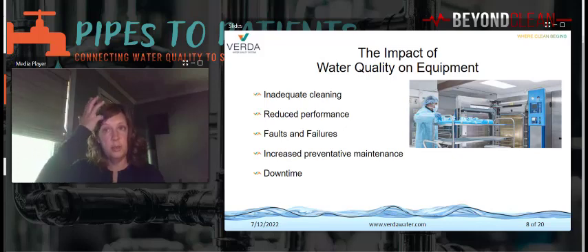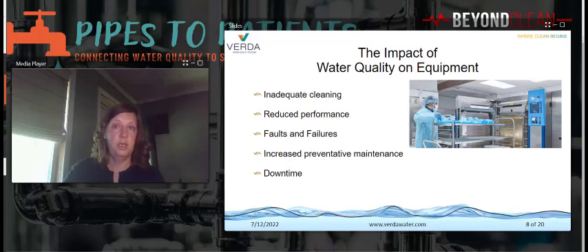Hard water scale also impacts the performance of water heaters and washer disinfectors, ultrasonic cleaners, and sterilizers with onboard boilers. Requiring more frequent replacement can ultimately result in damage, costly repairs if left unchecked. Endoscopy reprocessing equipment may also require some pre-water treatment for their feed water. Water treatment equipment often requires treatment to ensure optimal performance.